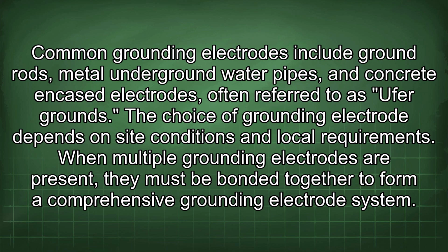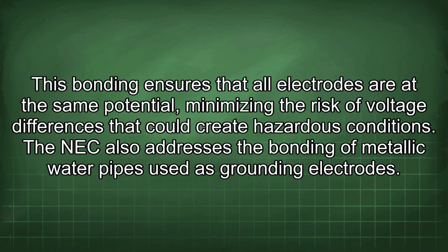When multiple grounding electrodes are present, they must be bonded together to form a comprehensive grounding electrode system. This bonding ensures that all electrodes are at the same potential, minimizing the risk of voltage differences that could create hazardous conditions.